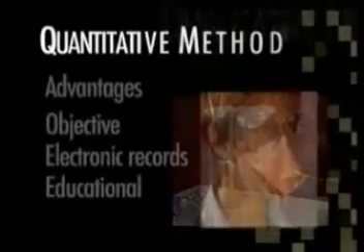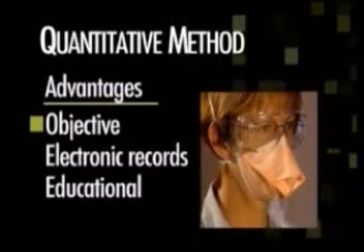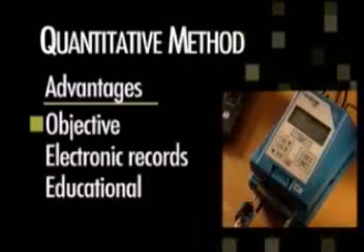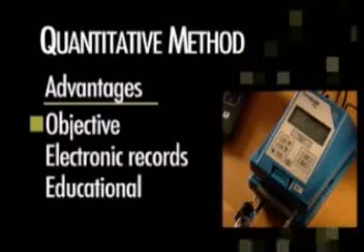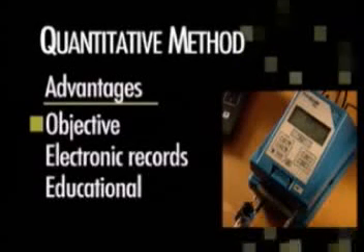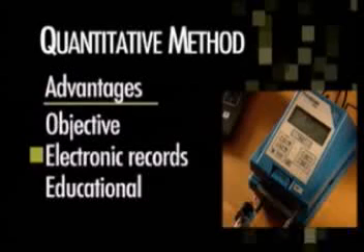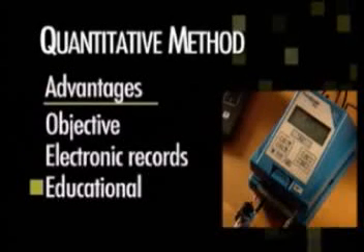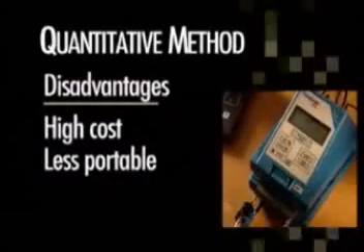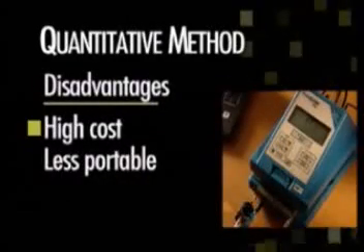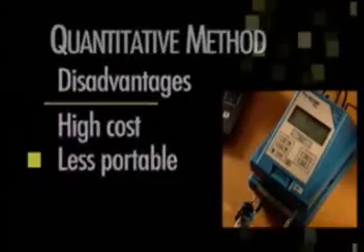Advantages of the quantitative method include that it is an objective test using an instrument to measure the particle count behind the mask. The results do not rely on responses from the person being tested. It provides an electronic record that can be stored and printed, and can be used as an educational tool to demonstrate the effectiveness of the fit of the mask. Disadvantages include that it is a relatively expensive instrument and can be cumbersome to transport.